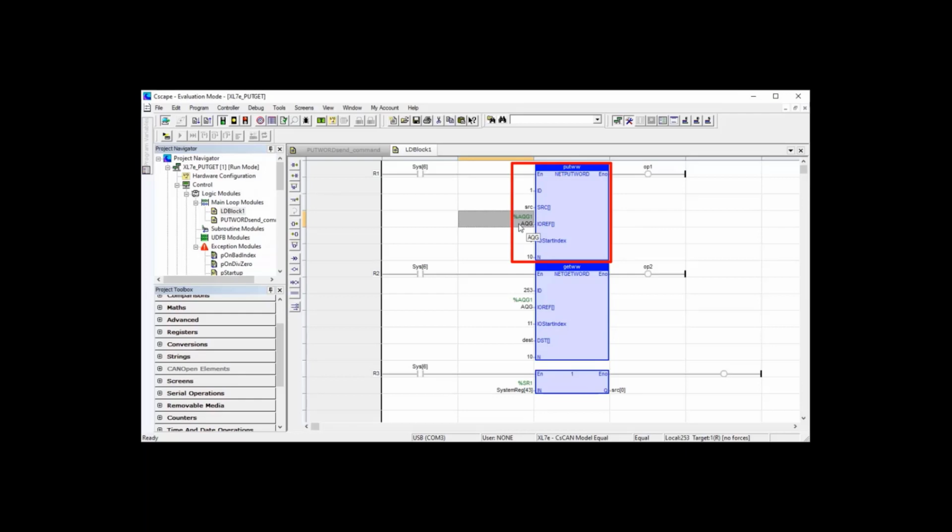IOREF specifies the starting IOREF, which must be AQG 16-bit or QG, which is 1-bit, Cscan networking data. IO start index is the start index for the IOREF. For example, to transmit the data starting at AQG1, then specify 0 here. N is the number of words to be transmitted.